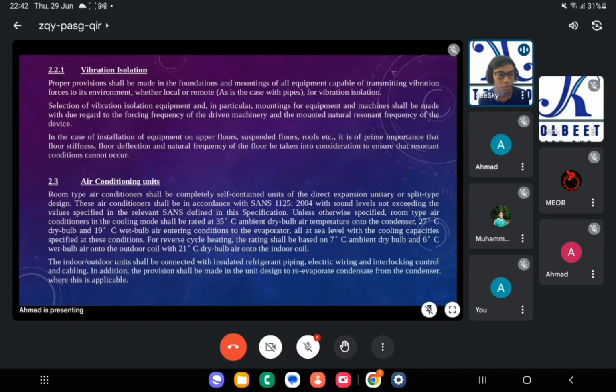2.2.1 Vibration isolation. Proper provision shall be made in the foundation and mounting of all equipment capable of transmitting vibration force to its environment, whether local or remote as in the case with the pipe. For vibration isolation, selection of vibration isolation equipment and in particular mounting for equipment and machine shall be made with due regard to the forcing frequency of the driven machinery and the mounted natural resonant frequency of the device. In the case of installation of equipment on upper floor, suspended floor, roof, etc., it is of prime importance that floor stiffness, floor deflection, and natural frequency of the floor be taken into consideration to ensure the resonant condition cannot occur. 2.3 Air conditioning unit.